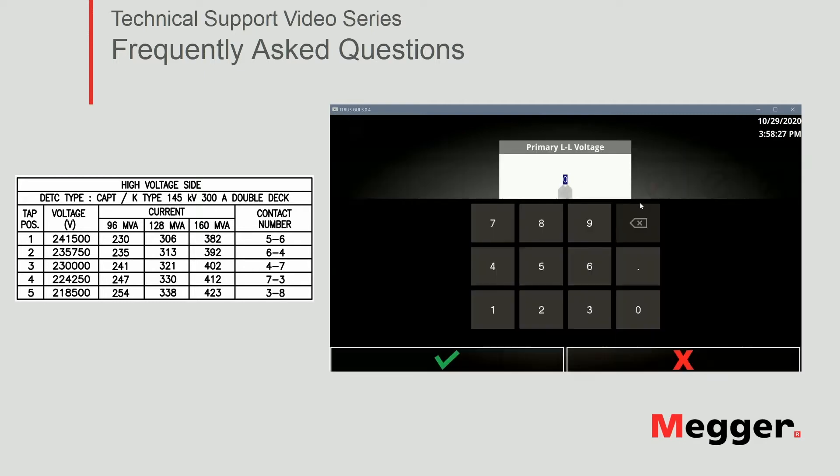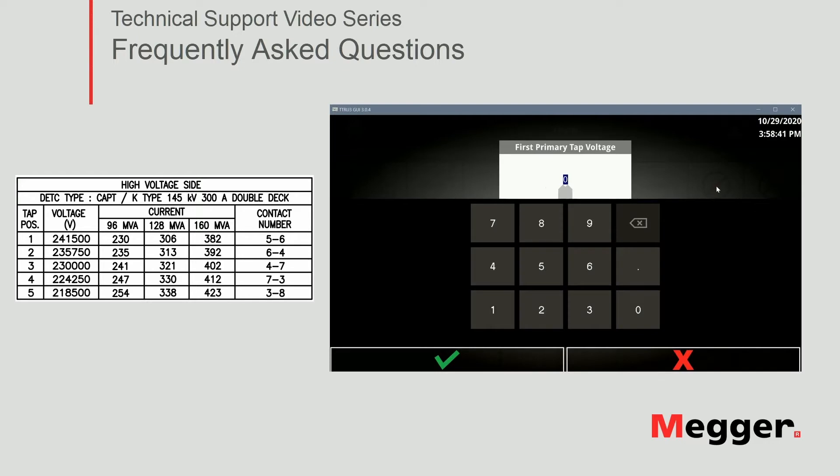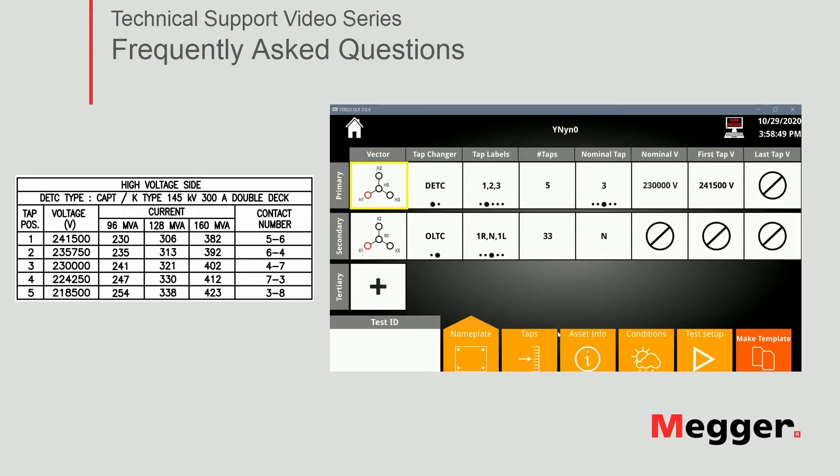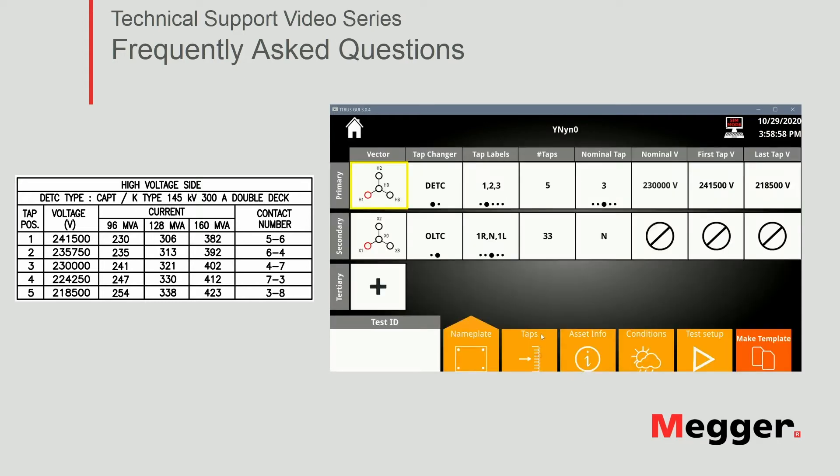We click on nominal voltage. We see it's 230 KV. Remember the voltage units in the settings in the software are volts. So I filled that out. Our first tap is 241,500 and our last tap is 218,500 volts.